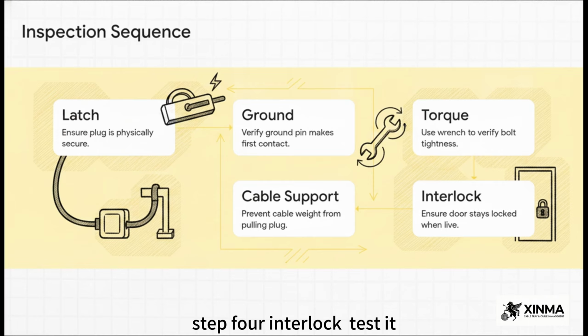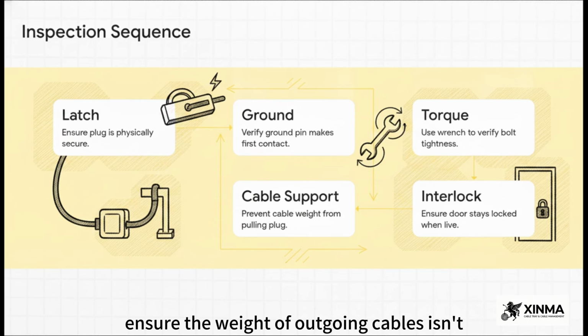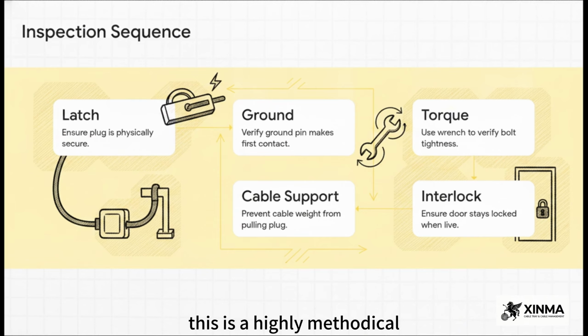Step 4. Interlock. Test it. Make sure operators cannot open the door while the system is energized. And Step 5. Cable support. Ensure the weight of outgoing cables isn't pulling down on those plug connections. This is a highly methodical, mechanical verification process. It leaves zero room for guesswork.